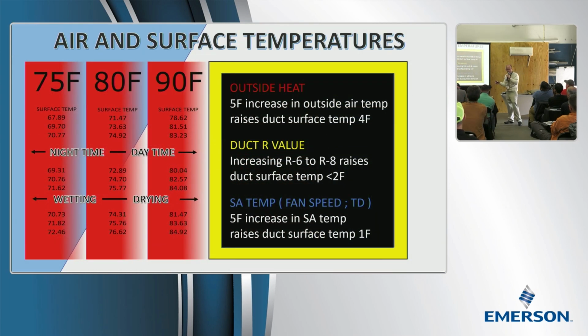So here's the summary, and this is what you get when you actually spread it out and look at it. A 5-degree increase in your outside air temperature raises the surface temperature of the ducts 4 degrees, and it is the biggest factor. So for example, that explains why a parking garage is so hard to deal with. You got any radiant heat in a cold parking garage where you got lots of air going through the parking garage because it's got these big fans for the car exhaust, but it's underneath a cold slab. That's a duct that wants to sweat, whereas look how much difference it makes with a little bit of heat.